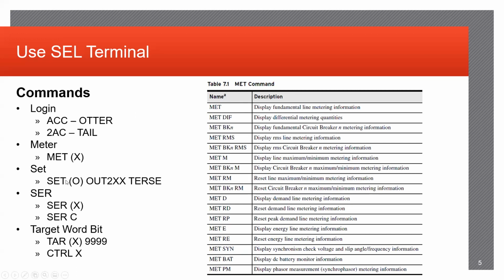The set command is extremely useful when testing certain elements, going back to what we discussed earlier based on the spare output. This is how you'll utilize that spare output when setting up your test plan. Say you're testing a 51 GP element and you want to associate that to an output so that your test set can understand when it gets picked up. You would be going into the terminal using the set command, identifying the output that you are plugged into, and utilizing the element that you're going to be testing at the end here.